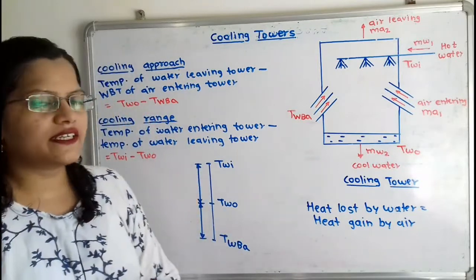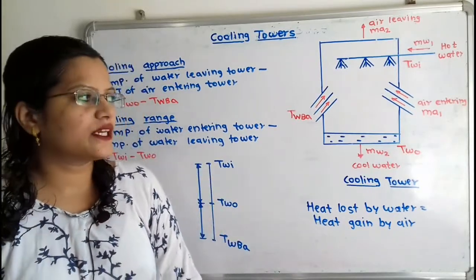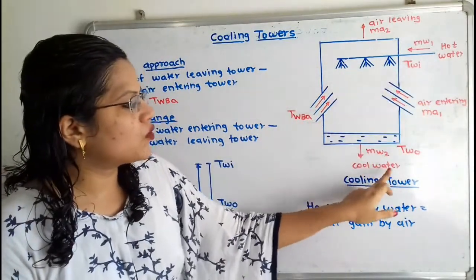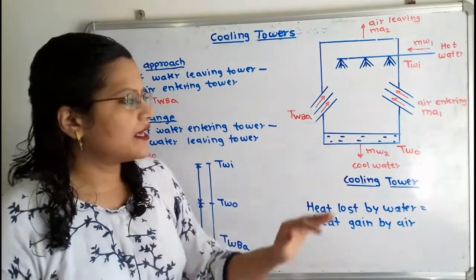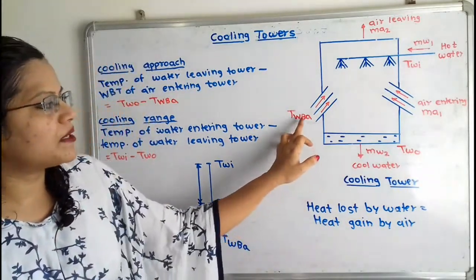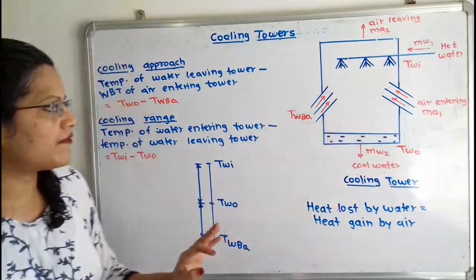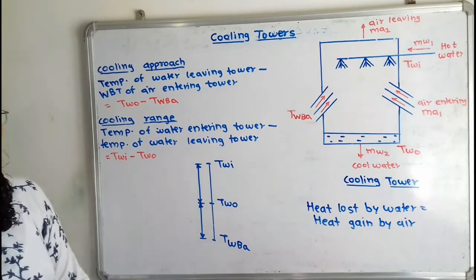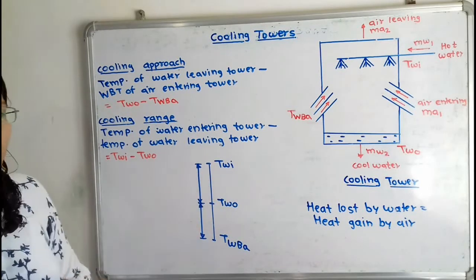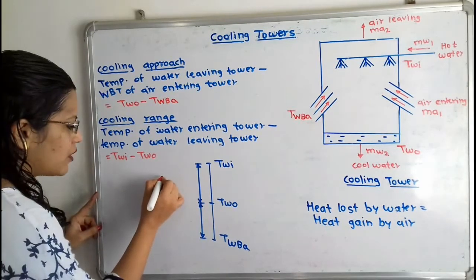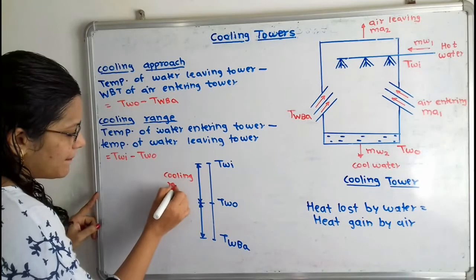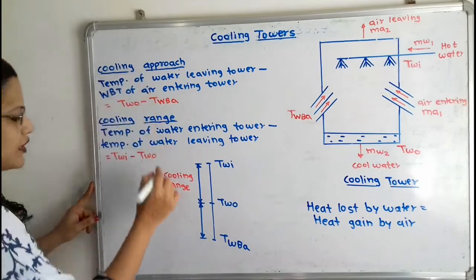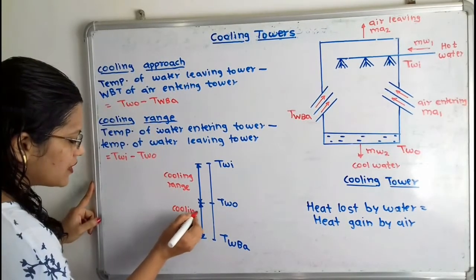If we plot these three temperatures, the hot water has the highest temperature (TWI). Lower than this is the cold water leaving the cooling tower (TWO). Then we have the wet bulb temperature of air (TWB-A). The difference between inlet water temperature and outlet water temperature is known as cooling range, and the temperature difference between outlet water and wet bulb temperature of air is known as cooling approach.